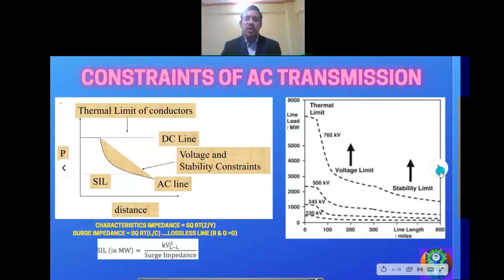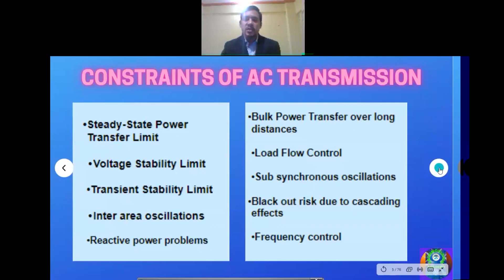Also, there are many more constraints, like steady state power transfer limit, then voltage stability limit, transient stability limit, inter-area oscillations. Again, we have reactive power issues, bulk power transfer over a longer distance, load flow control, subsynchronous oscillations, which are generated in the system because of the capacitors present in the electrical system and on the generator side. When the frequency of the generator and the frequency of your electrical device match each other, then subsynchronous resonance forms. But by using FACTS technology, we can overcome these subsynchronous oscillations. Then blackout risk due to cascading effects can also be overcome by FACTS technology. Frequency can be controlled by controlling these devices. So these are the constraints of AC transmission, but we can still overcome them by FACTS technology.